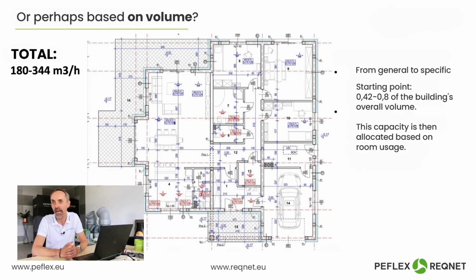But this provision applies to residential spaces or collective residential buildings, such as hotels, hostels, or guest houses. So there is no legal reference for this application. However, as I mentioned, this method, meaning by room volume, is very often used among installers, among investors, as a way of asking how to select a recuperation system.